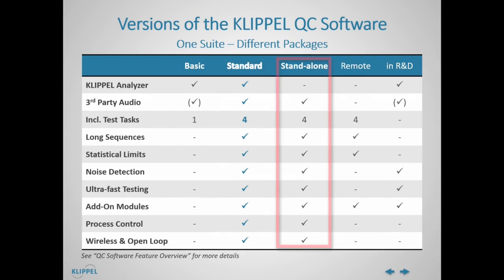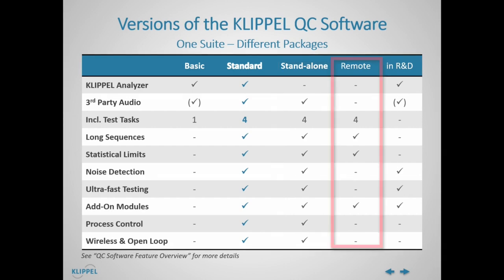The QC Standalone version provides a very similar feature set, but unlike QC Standard it is dedicated for testing without Klippel Analyzer hardware. This version only requires a licensed dongle and can be applied for open loop or closed loop testing with any third-party sound card or even based on WAV files only. The QC Remote Configuration license is dedicated for test and limit setups for many PCs without test hardware connected.